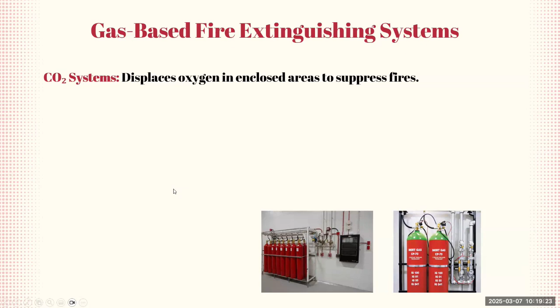Or we could have inert gas systems, because in some cases CO2 could be harmful to operators if inhaled in large amounts. So we use different types of gases like argon, nitrogen, or clean agents for fire protection. This is also ideal for sensitive equipment like server rooms, which hold information that needs to be left unharmed.